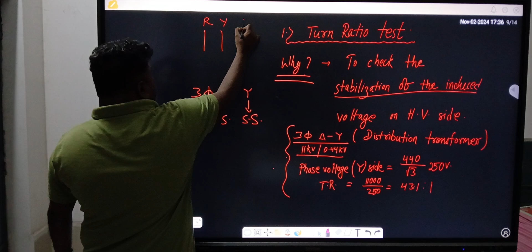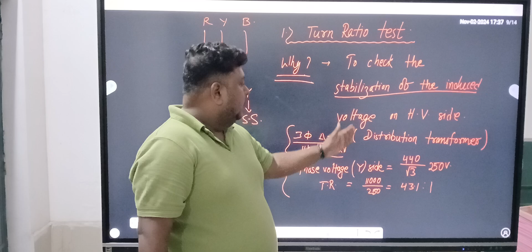So any one of the phase voltage means first, see here, why star side? Here it is written phase voltage star side. In bracket I have written star side. You know the formula for phase voltage, if it is delta connected and we are converting it into star, then what is the formula? Line voltage by root 3, VL by root 3 will be the phase voltage for star. So that is why we are dividing the required voltage, that is we are applying voltage 440 volt.